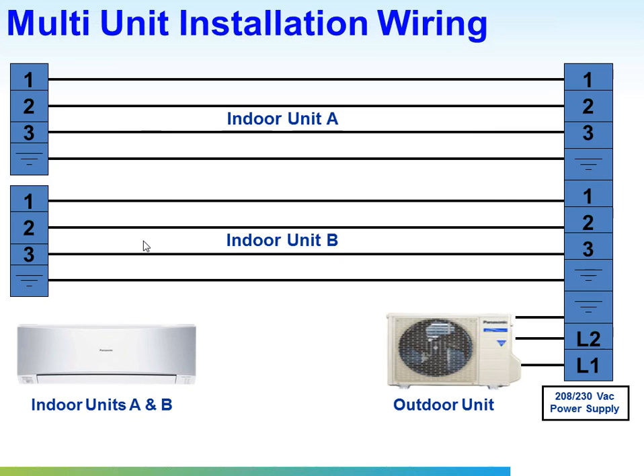The multiple units, the multi-zone units, are also wired in a similar fashion. You power the outdoor unit, and the outdoor unit powers the indoor unit in both cases here. So we have wired terminals on the outdoor unit for both indoor unit A and indoor unit B as listed here. And so in a case where we have a 4-zone model, there would be 4 sets of terminals for those additional 2 units.